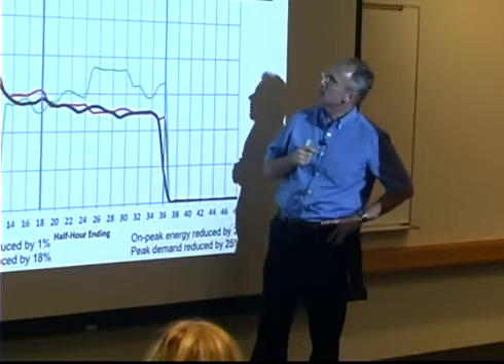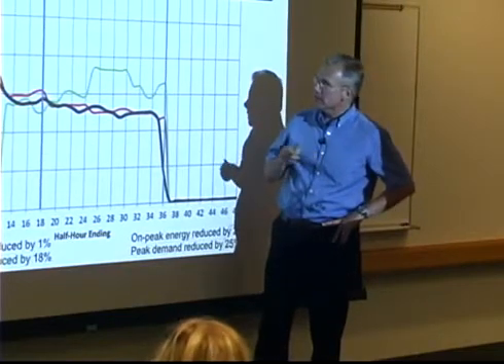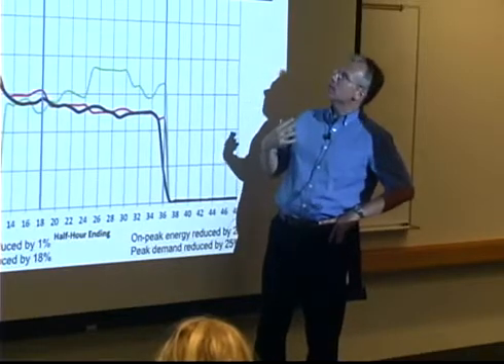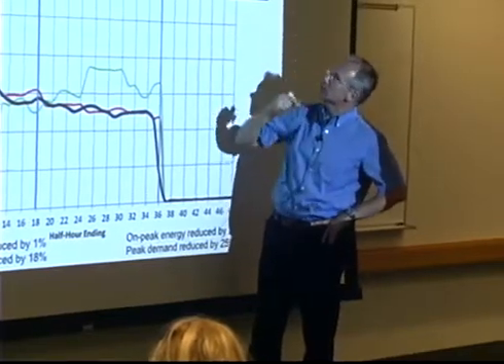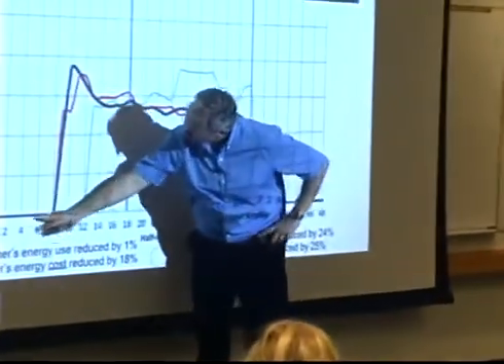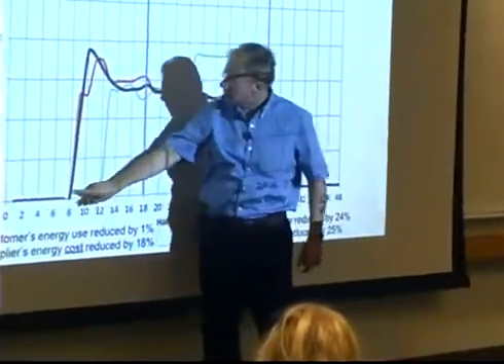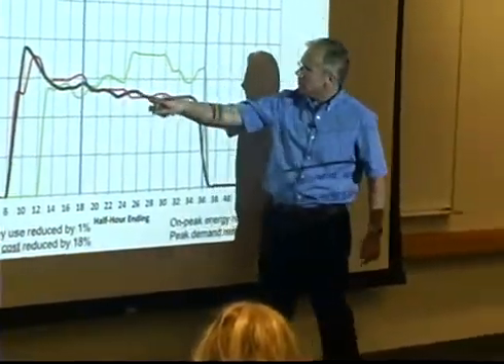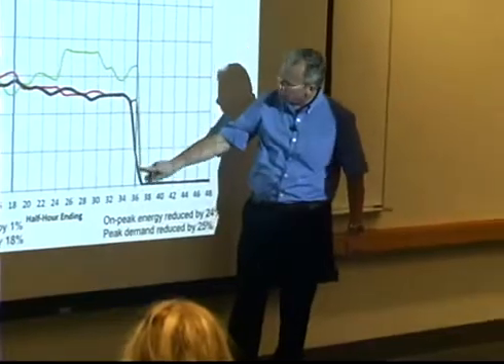Between 9 and 6 p.m. the peak demand period occurs. So the strategy that the optimizer came up with for September 2010 looked like the red line here. It started the system at 4 a.m. You start pre-cooling the building, and it basically predicted the consumption pattern shown in red here.